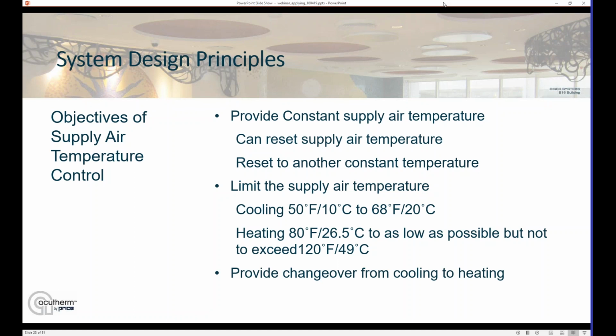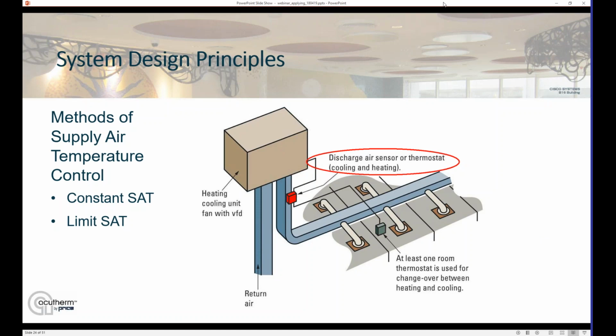So the source of heating and cooling needs a means to know when to turn on the heating. As I mentioned, the diffusers are using the supply air to determine the mode, so we need something to make that decision for the system. So for our first two goals there, as far as a constant supply air temperature and to limit supply air temperature, a discharge air temperature sensor on our source of heating and cooling is the best way to do that. And if that's a modern, more sophisticated unit where you can modulate the cooling, modulate the heating, this works very well because you can pick your supply air temperature. The unit will control to that. And when you want to pick another one, it'll control to your new temperature.